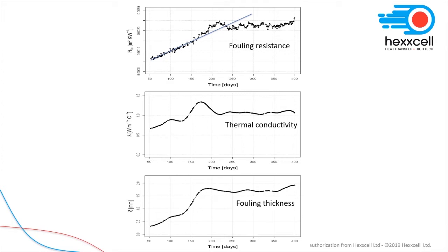In fact, what was happening during this period was that an upset in an upstream unit, the desalter, generated a rapid fouling event in the heat exchanger, accumulating material at a much higher deposition rate and a higher thermal conductivity than previously experienced. However, this event is not detected by monitoring the fouling resistance alone, since we now have a thicker deposit layer at a higher thermal conductivity, which, from strictly a thermal point of view, produces the same overall effect of a smaller layer at a lower thermal conductivity.